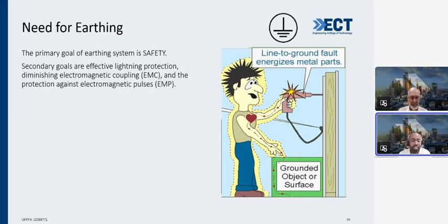But just to clarify: grounding is connecting all the live parts of an equipment to earth. These parts will carry currents under normal conditions - so the neutral part, if we were to speak about the neutral conductors or the grounded phase conductors. Whereas earthing is connecting the metallic parts of the equipment to earth, and these parts wouldn't carry current under normal conditions. So grounding is more about the protection of the overall system or the equipment, whereas earthing is primarily about the protection of the workers, of human life, or to avoid hazards to human life.